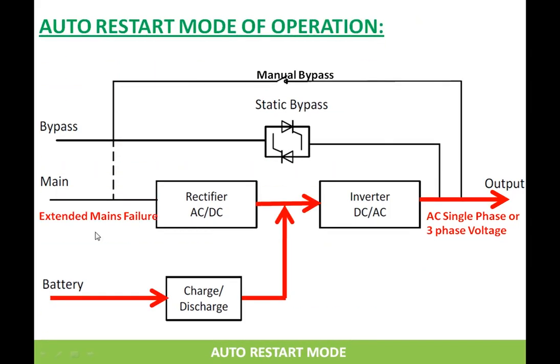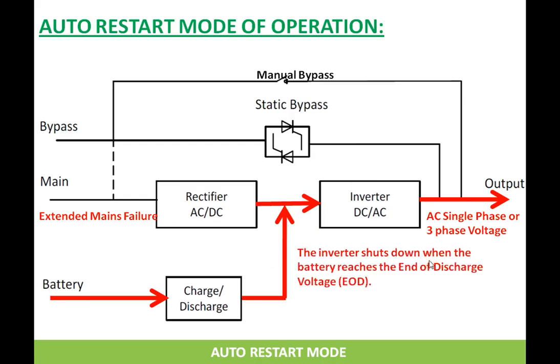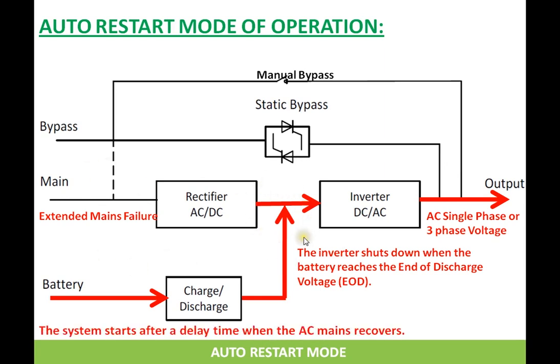The other mode is the auto restart mode. The UPS goes to this mode when incoming mains fails for an extended amount of time. When mains fails, the UPS transfers to battery, but the battery can only support the UPS for a limited time depending on battery age. When the battery voltage reaches the end-of-discharge voltage — for a 12V battery that is 10.5V — the UPS detects this and shuts down the inverter, so UPS output is no longer available. When power recovers, there is a delay before switching on the inverter, because the battery is completely discharged and takes more current for charging. This delay prevents the UPS from tripping, and this is the auto restart mode.